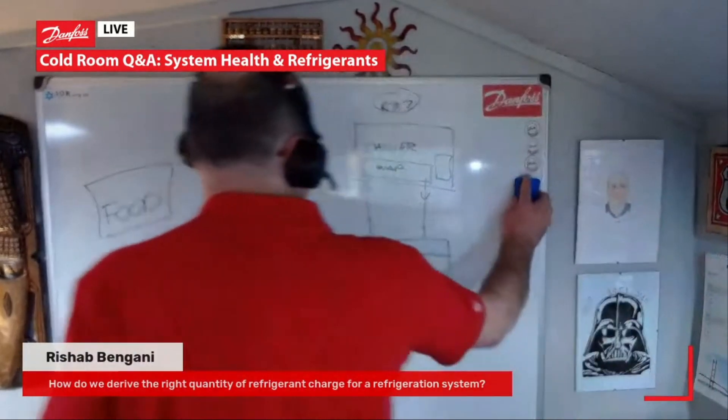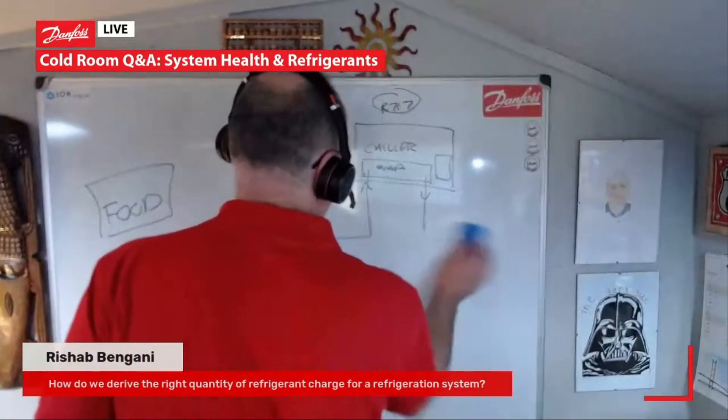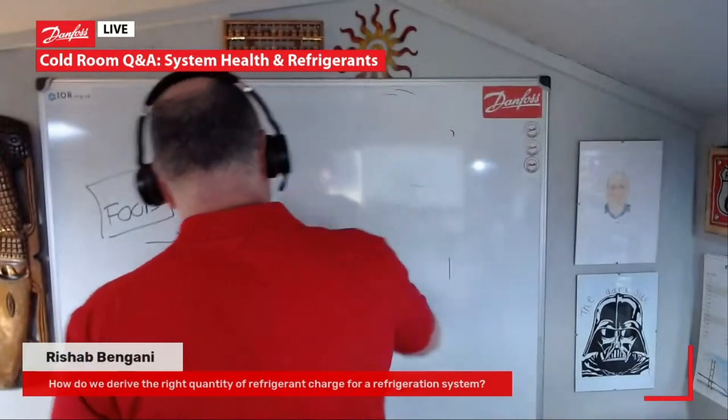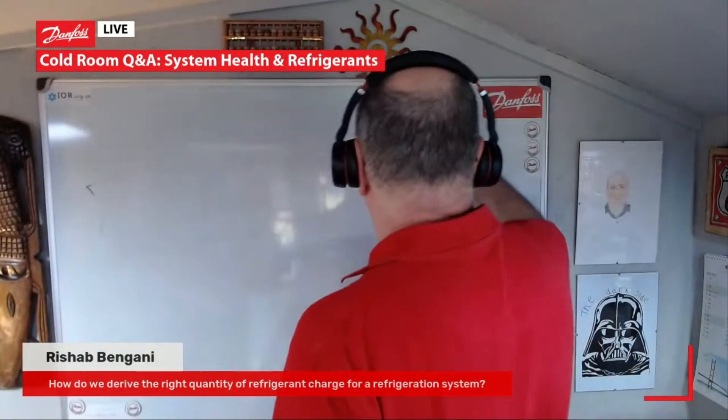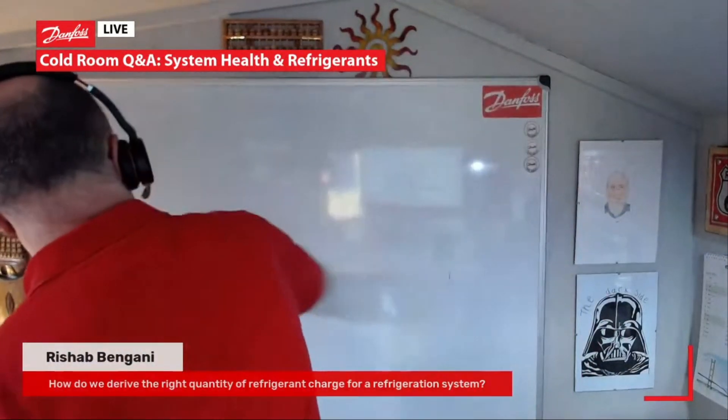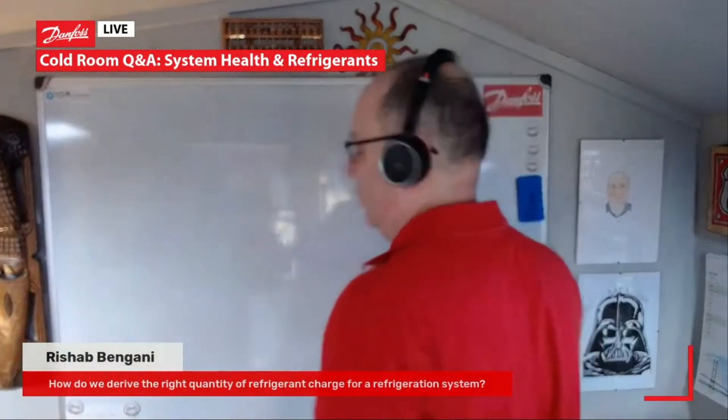Charge is an interesting discussion. When we talk about refrigerant charge, basically you can estimate your charge of your system by the length of the liquid line and the size of that liquid line. And that will give you a base quantity, if you like.